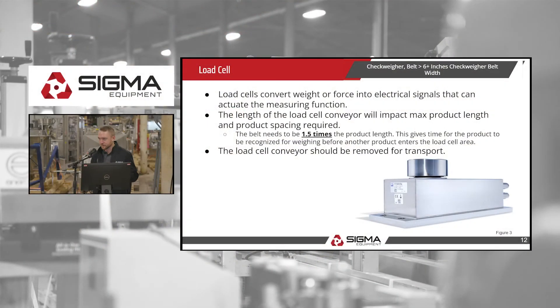Now, onto the load cell — the most important part of this equipment. Load cells convert weight or force into electrical signals that actuate the measuring function. The length of the load cell impacts the maximum product length and product spacing required. Importantly, the load cell conveyor must be 1.5 times the product length — this gives the product enough time before the next product comes in to be weighed. Also note that the load cell conveyor should be removed for transport.